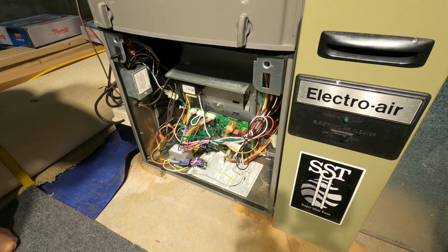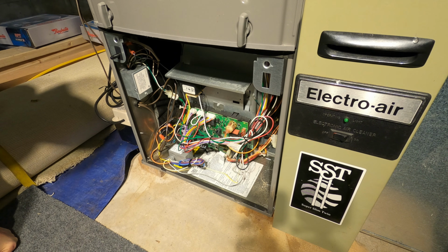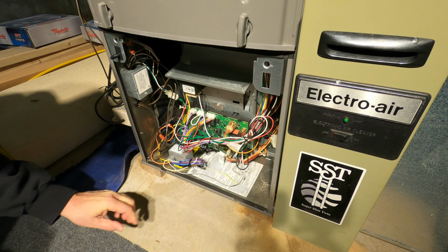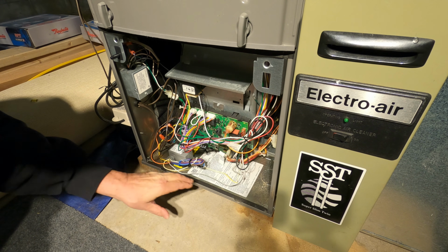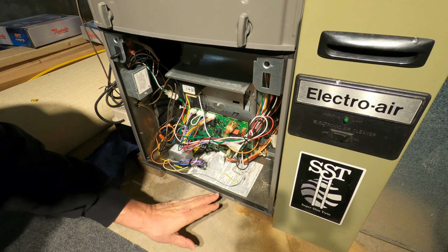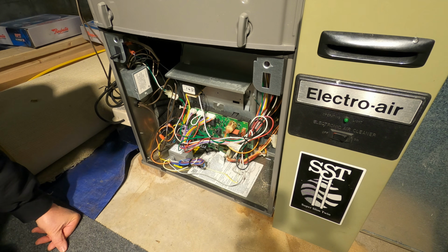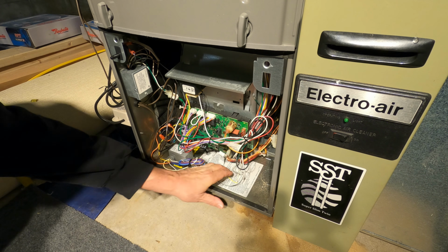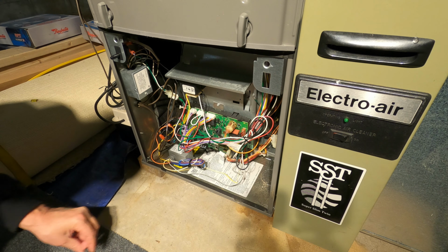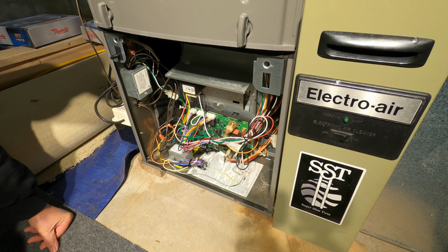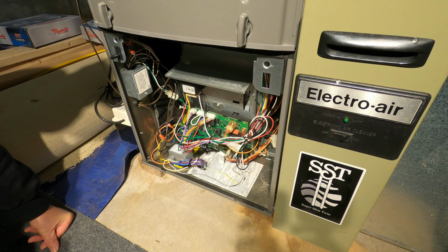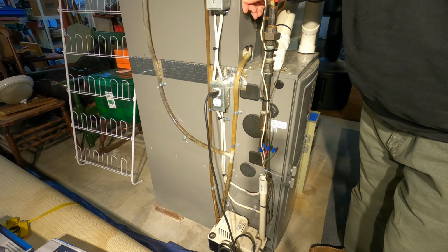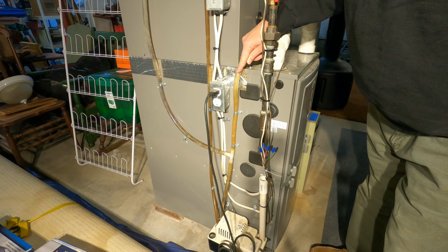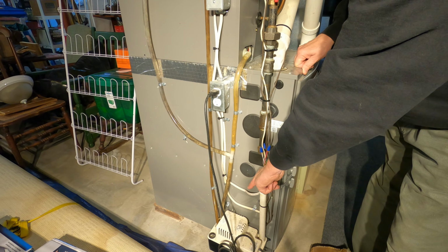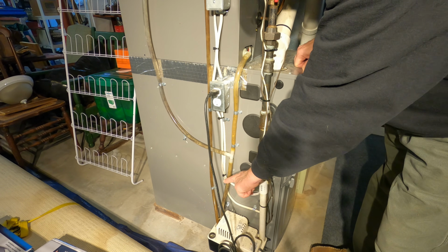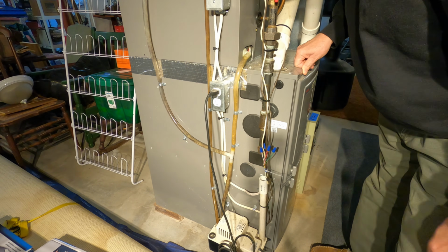One helpful commenter said the relay shouldn't be mounted on the bottom of the furnace cabinet. He pointed out that if the AC evaporator, which is on top of the furnace, should happen to ice up, water will drip down inside the furnace and pool up in the bottom, right where the relay is. So that could become a problem. And it actually turned out that the drain tube on the evaporator housing happened to clog up this summer. The evaporator housing has a drain point here that is plumbed into this tubing, which runs down into that condensate pump, and that pump takes it and pumps it up through this tube out over to the sump crock.